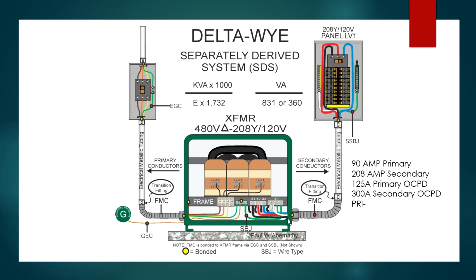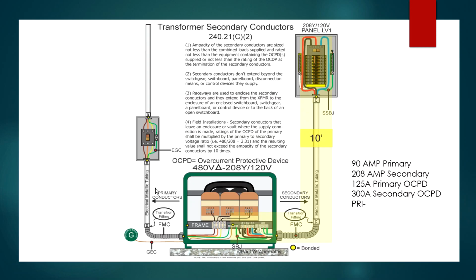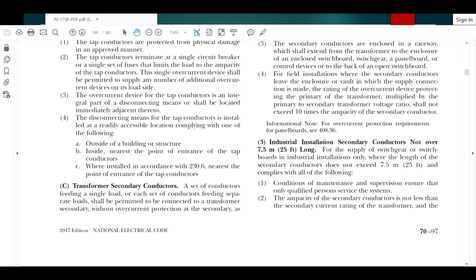Okay? And if that's the case, then they are actually feeders that are going out, and I would have to apply Article 215. It'd be 125% of the continuous and 100% of the non-continuous. But these are secondary conductors. There is no overcurrent protection right here, so we do have some length limitations that we have to worry about under the secondary conductor rule. All right, so let's go on and look at the 10-foot secondary conductor rule. Actually, before we look at this one, let's knock out of the way the first one, C1, which is the one that I said was very obscure.